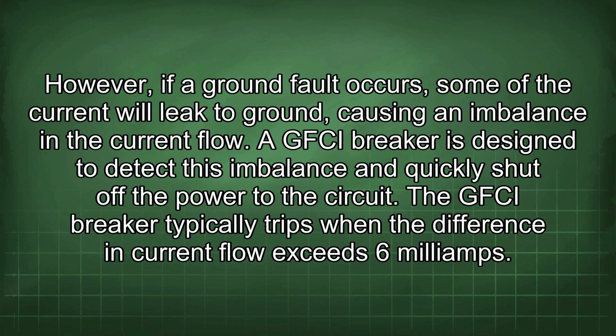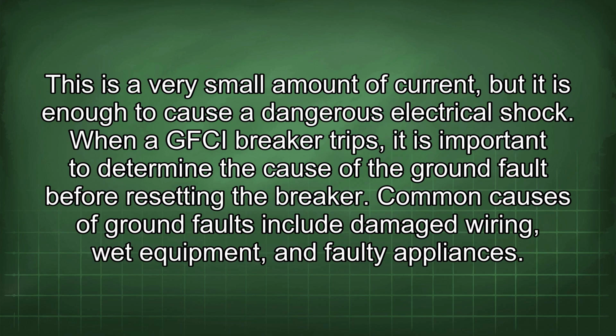A GFCI breaker is designed to detect this imbalance and quickly shut off the power to the circuit. The GFCI breaker typically trips when the difference in current flow exceeds 6 mA. This is a very small amount of current, but it is enough to cause a dangerous electrical shock.